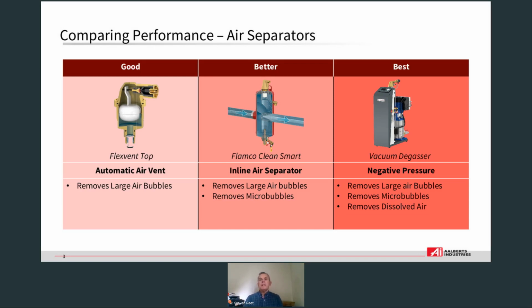The Vacumat Eco shown in the right-hand part of this slide is a unique product as it monitors both pressure and temperature. The degasser automatically chooses the most cost-effective vacuum for optimal deaeration. So it removes air at the rate of 1,000 litres per hour, and it's much better for the much bigger systems and particularly heat networks. We measure the temperature and pressure, so we operate to a much higher temperature and pressure range, all the way up to 90 degrees C maximum temperature at point of connection.